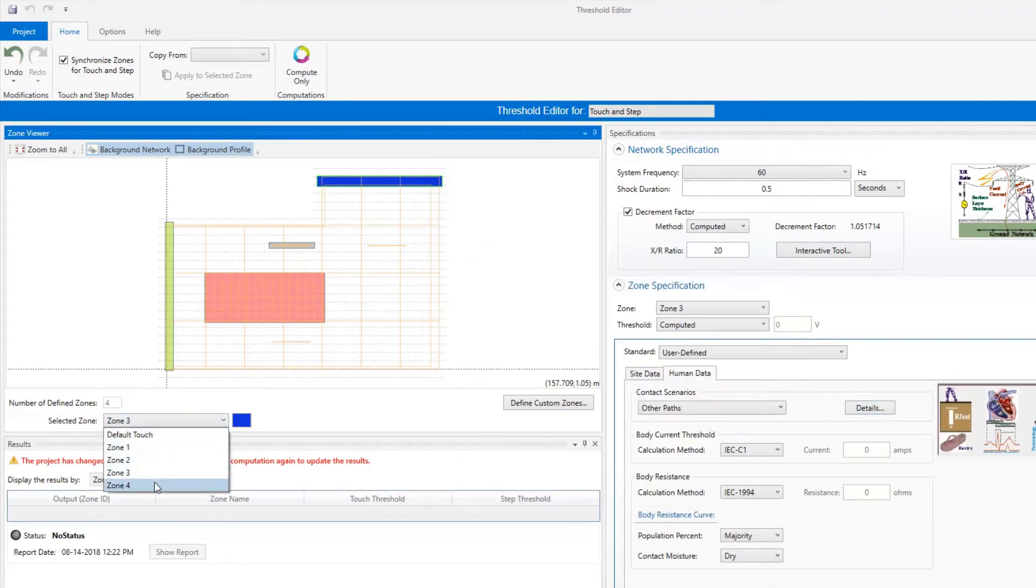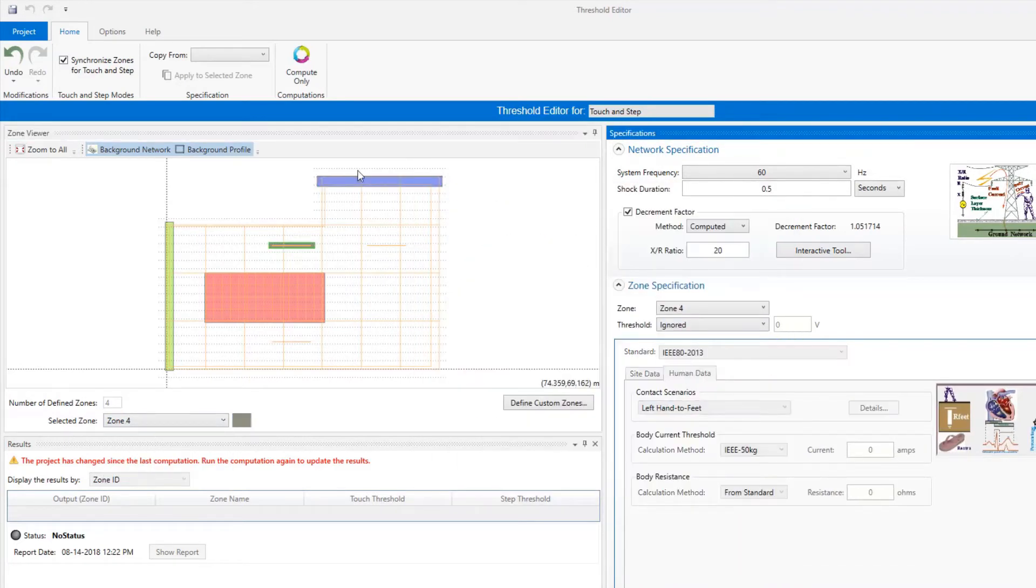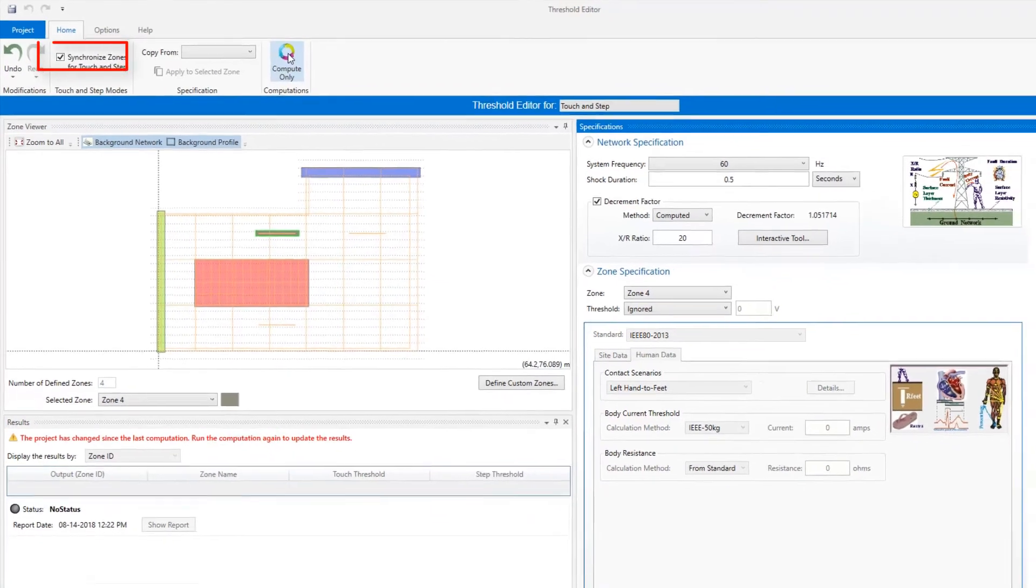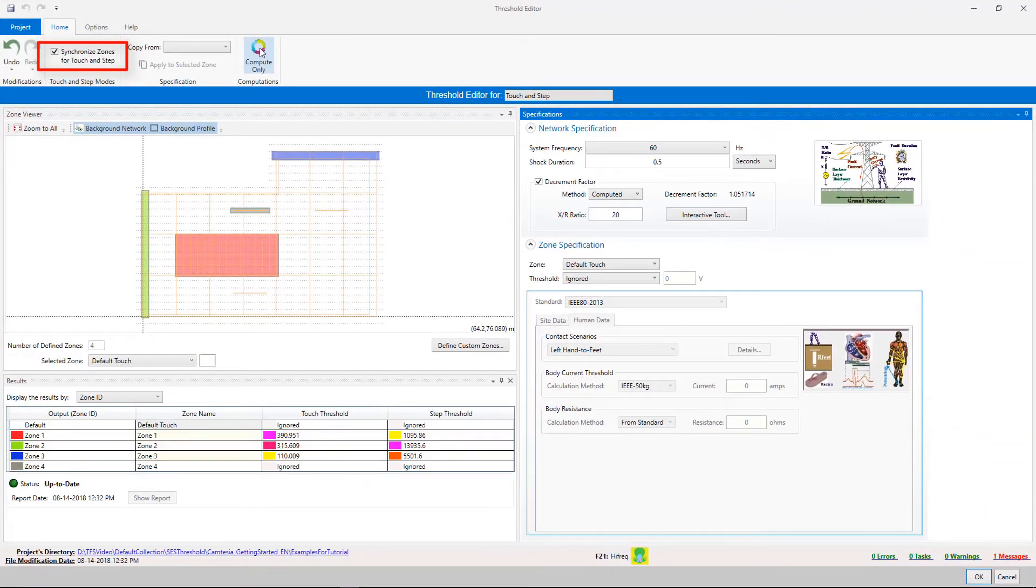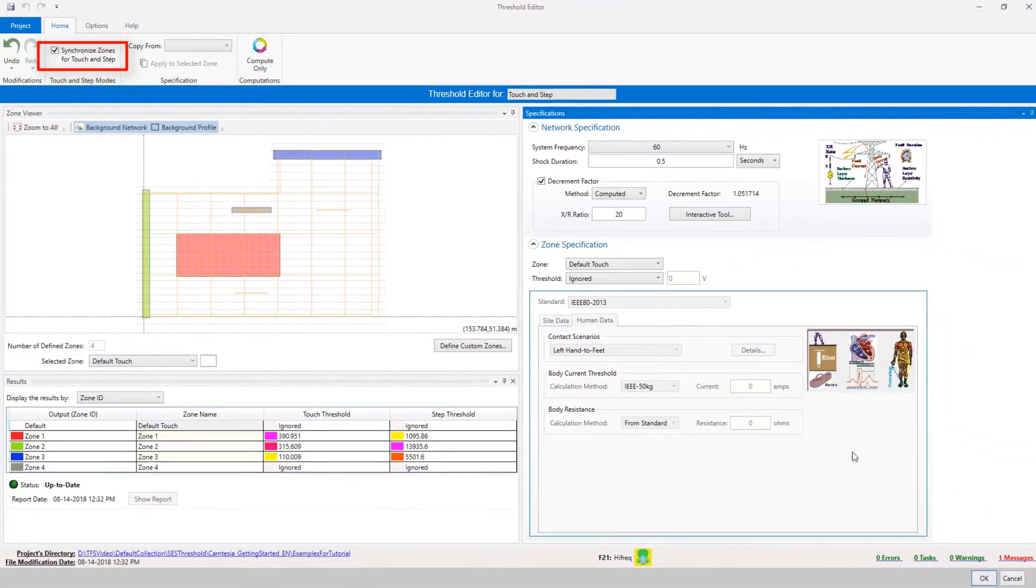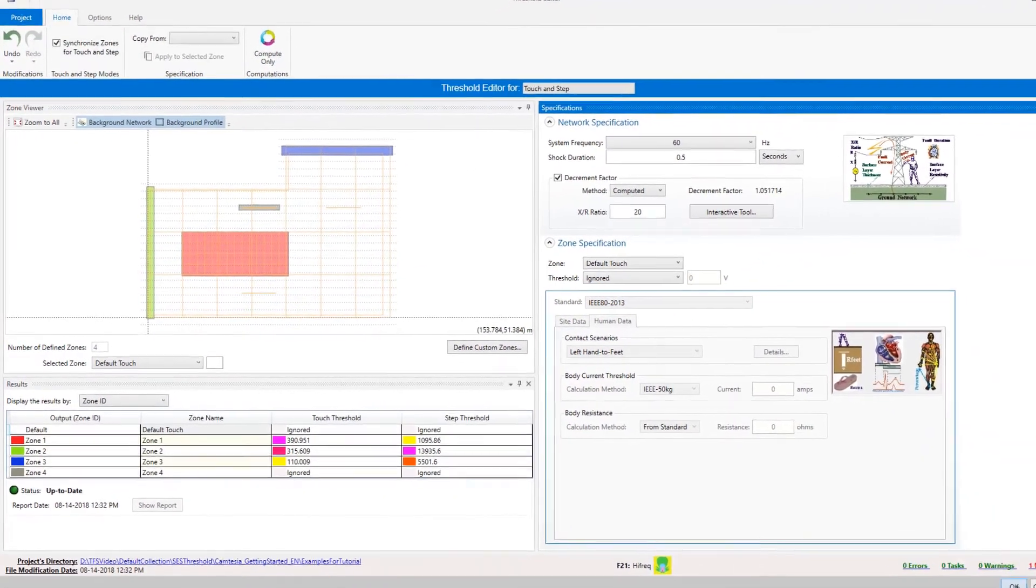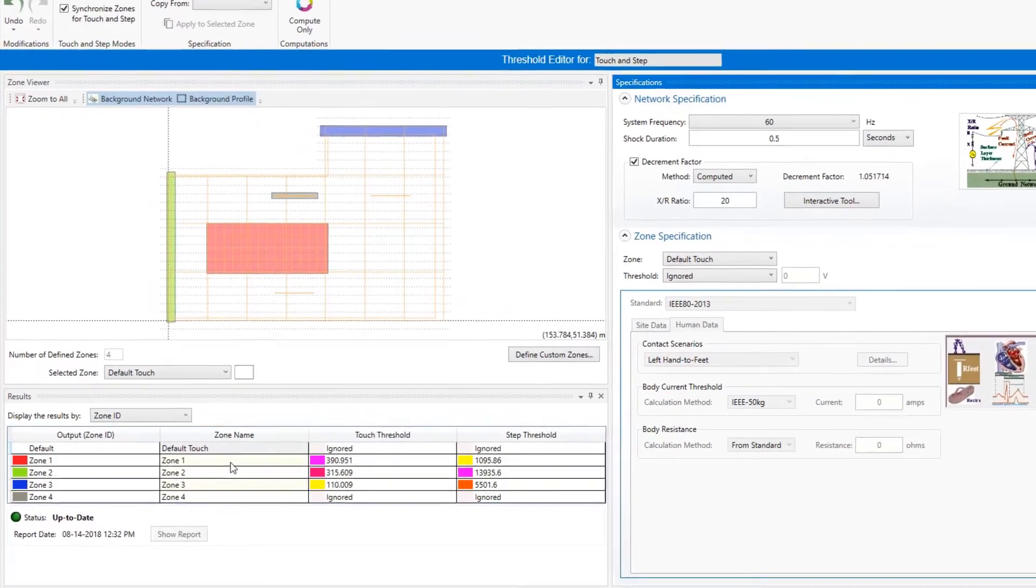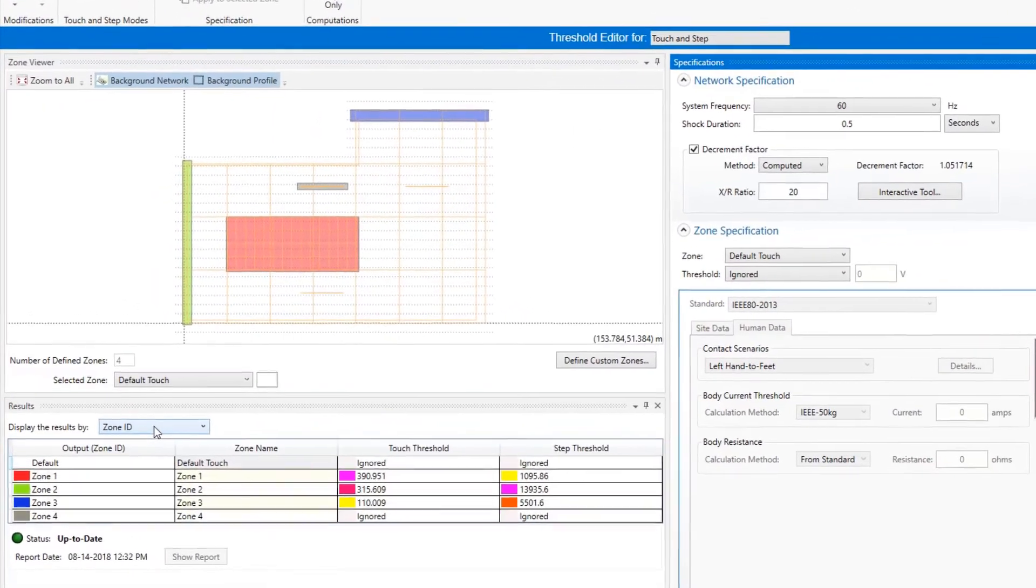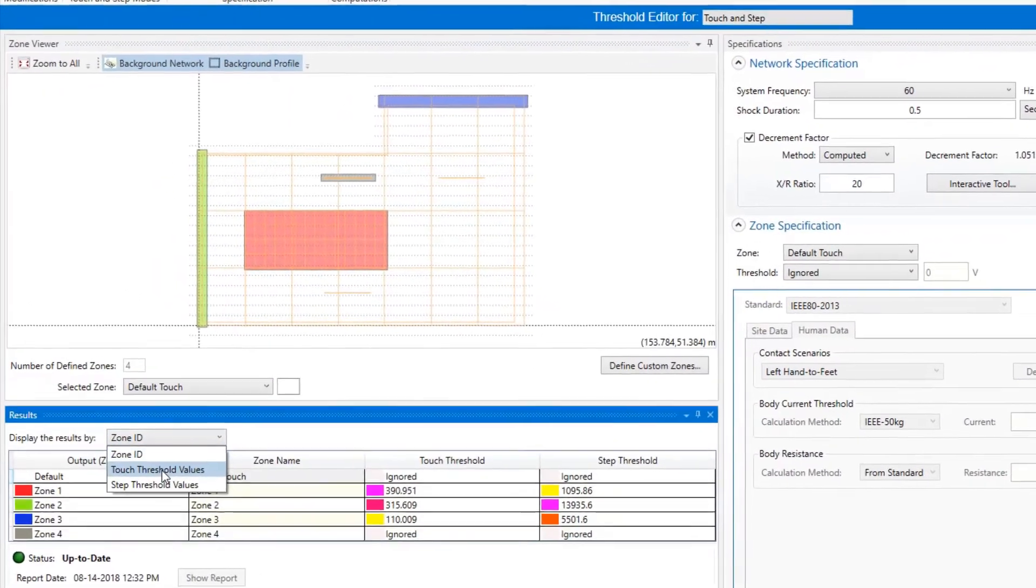Our next step is to compute the corresponding thresholds. As we have selected to synchronize the zone definitions between the touch and step, the table of results will display thresholds for both touch and step quantities.